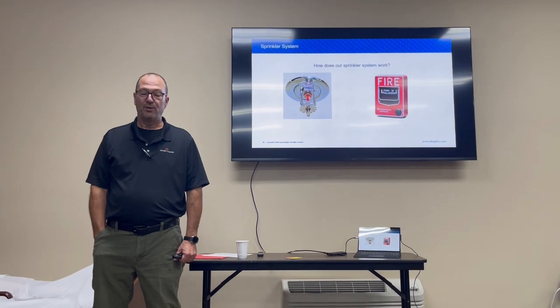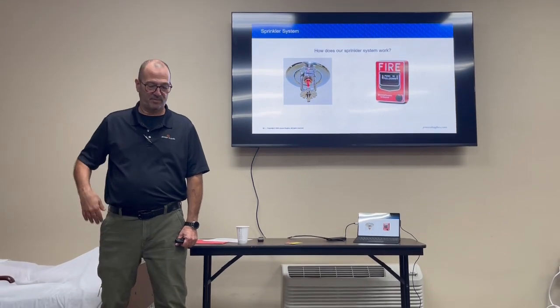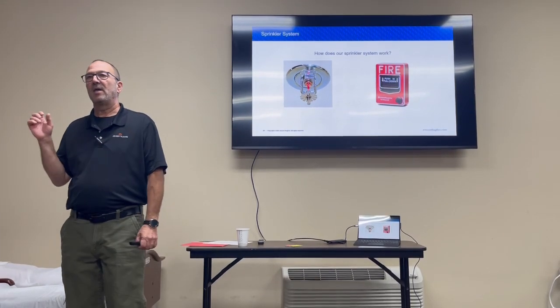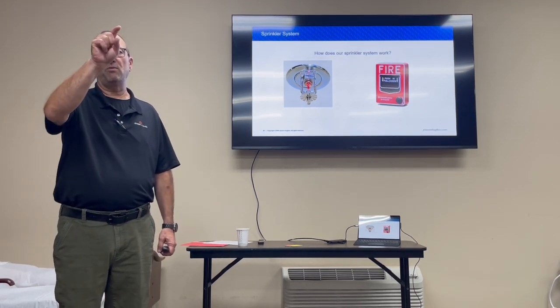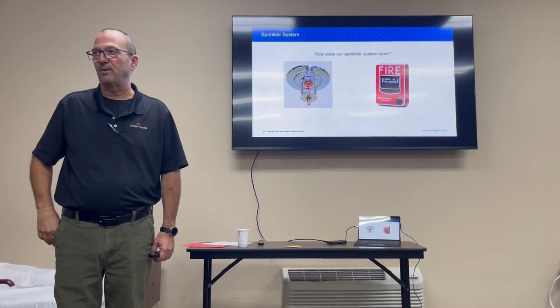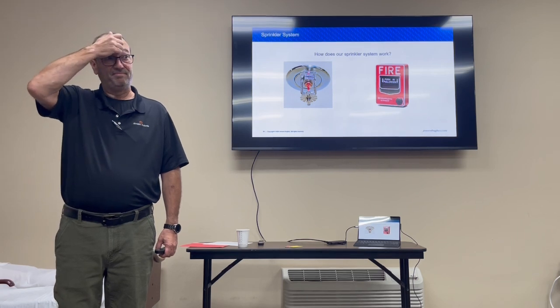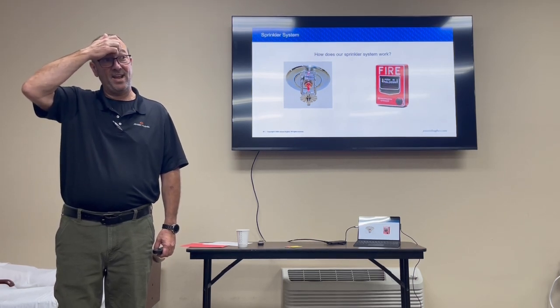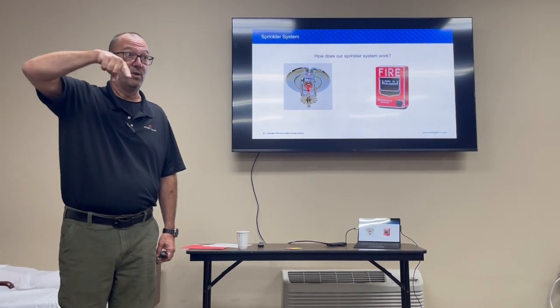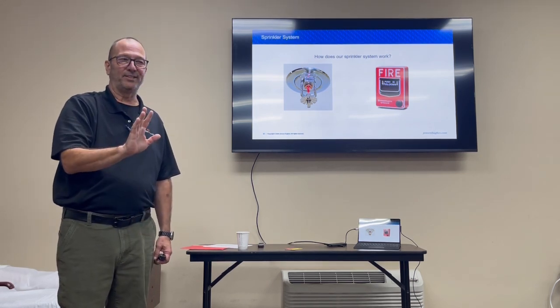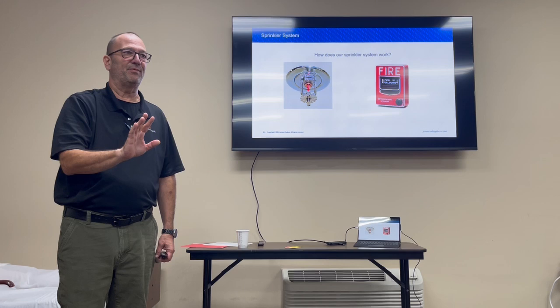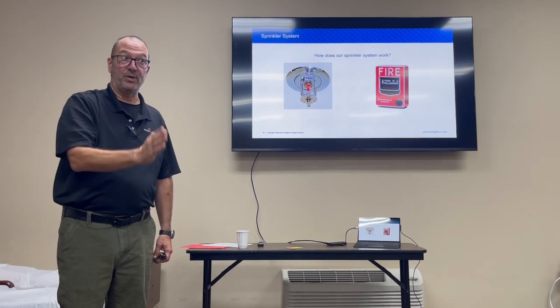It's gross. Now, sprinkler head activates. How long before the fire department is standing in front of that resident room to say, okay, the fire's out, we can shut the sprinkler down? 10 minutes. At least. They're probably here in that 10 minutes, but now they got to get to the room. So in 10 minutes, that's 200 gallons of water on the floor. Well, let's say realistically, it's probably close to 15 minutes, and that's 300 gallons of water.